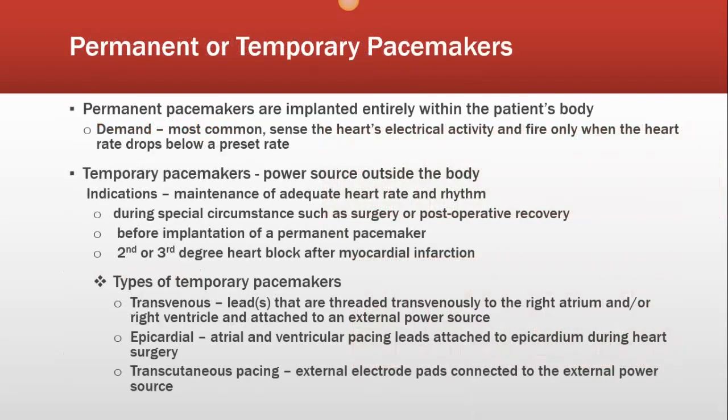Permanent or temporary pacemakers. So permanent pacemakers are implanted entirely within the patient's body. Most are a demand pacemaker. Basically, when they sense the heart's electrical activity and it needs a firing, they will fire. And generally, this is when the heart rate drops. There's a preset level with the pacemaker, so that once they go below a certain rate, the pacemaker is going to fire.